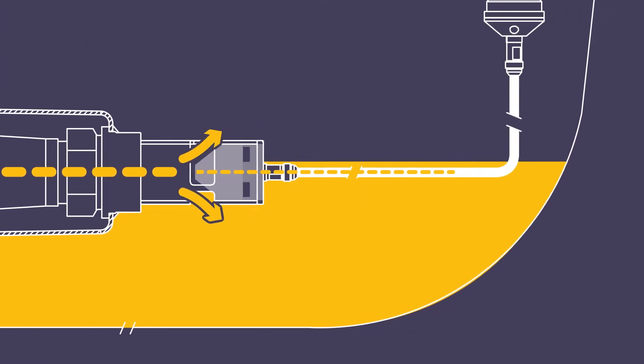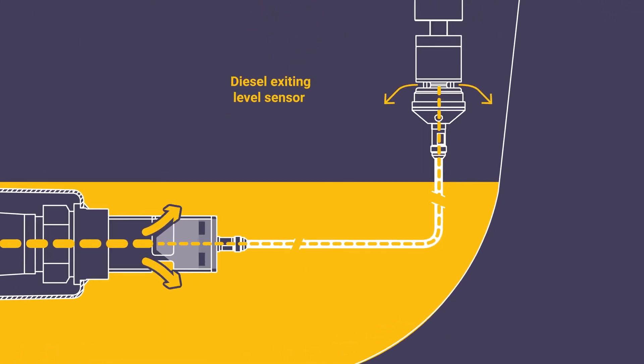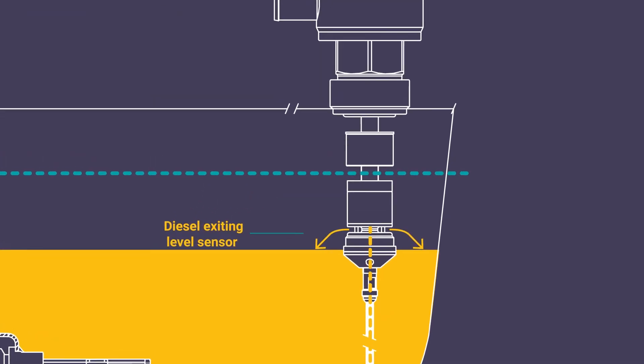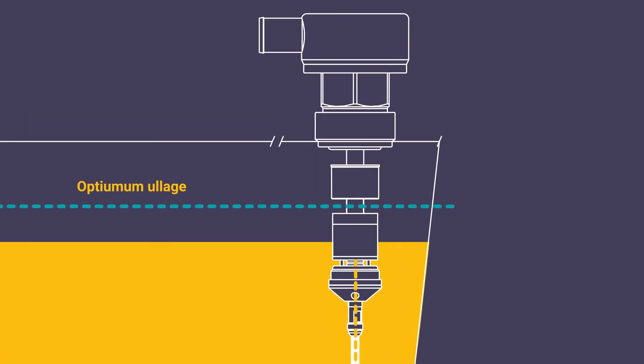A trickle of diesel travels from the flow control valve through the pilot line and out of the bottom of the level sensor. When diesel within the tank reaches the optimum ullage, it interacts with a balance element in the flow control valve.